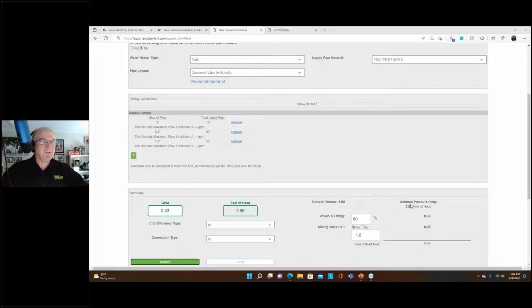It's not a goal, but if we're deadheading a teeny weeny little pump for 10 minutes or so, or actually, what's 5 minutes on, 10 minutes off. So the worst case scenario, we're going to run that pump. We're going to deadhead that pump. In the absolute worst case, we're going to deadhead that pump for 4 minutes and 59 seconds, let's say. That's the worst case scenario. It's fine. It's fine. Does Taco make a circulator with a 0.33 GPM?